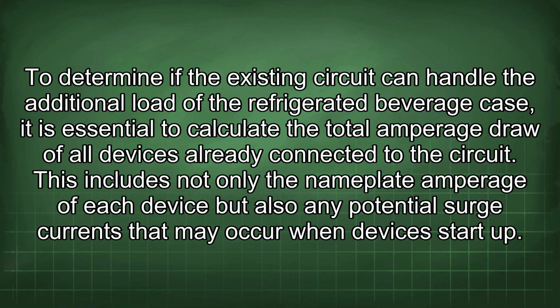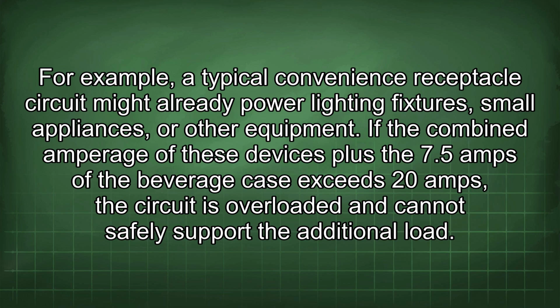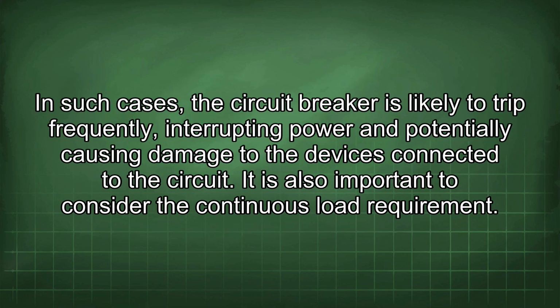This includes not only the nameplate amperage of each device, but also any potential surge currents that may occur when devices start up. For example, a typical convenience receptacle circuit might already power lighting fixtures, small appliances, or other equipment. If the combined amperage of these devices plus the 7.5 amps of the beverage case exceeds 20 amps, the circuit is overloaded and cannot safely support the additional load. In such cases, the circuit breaker is likely to trip frequently, interrupting power and potentially causing damage to the devices connected to the circuit.